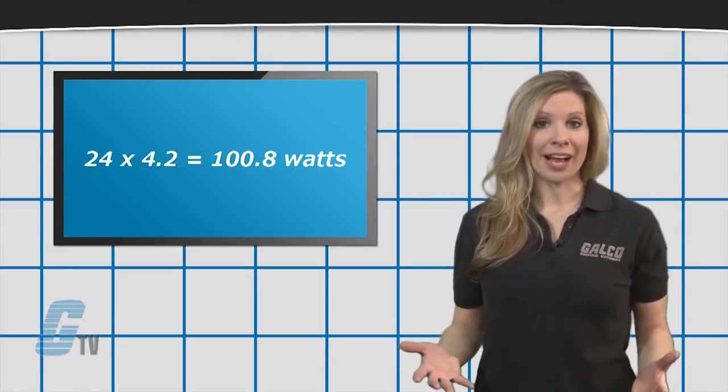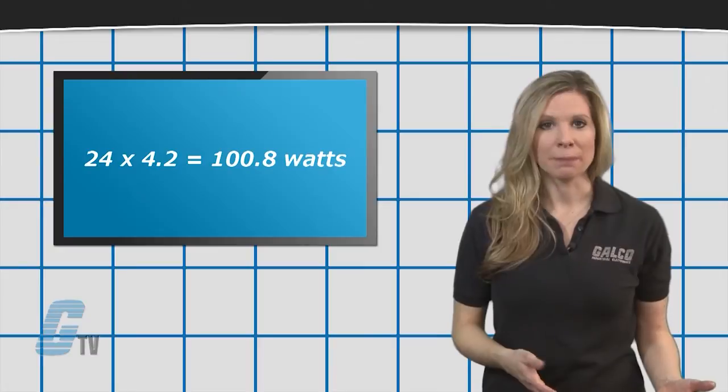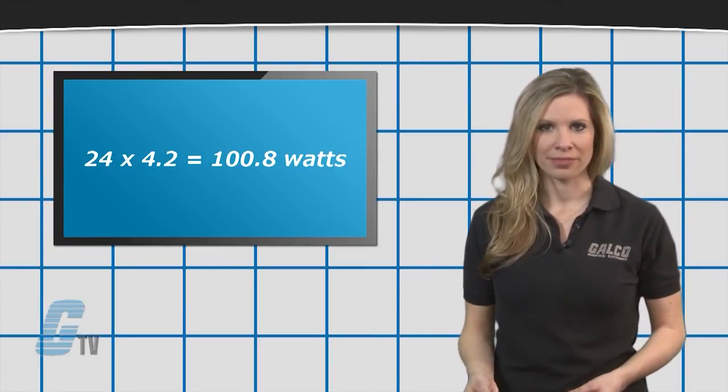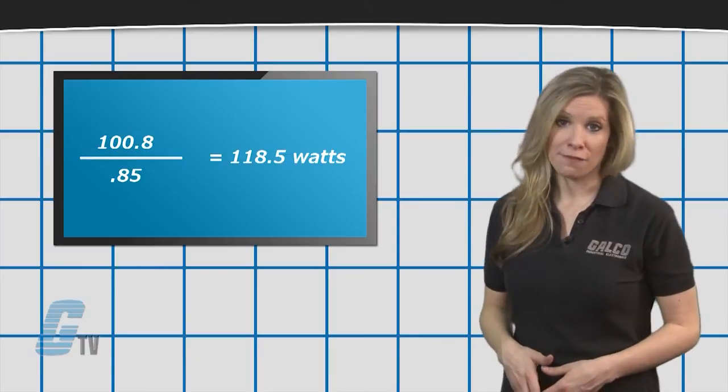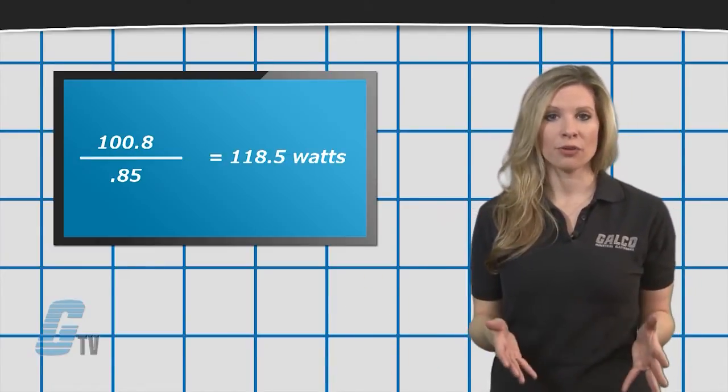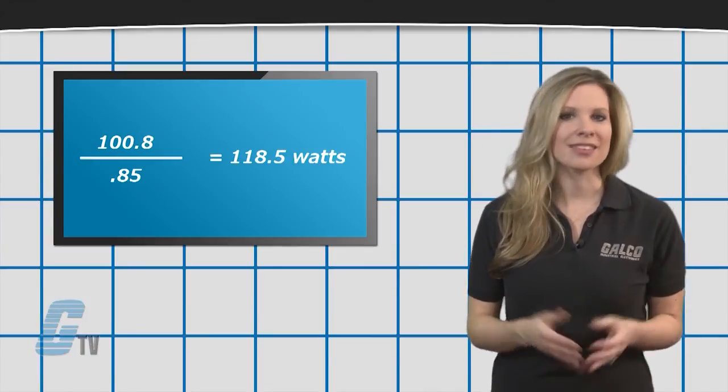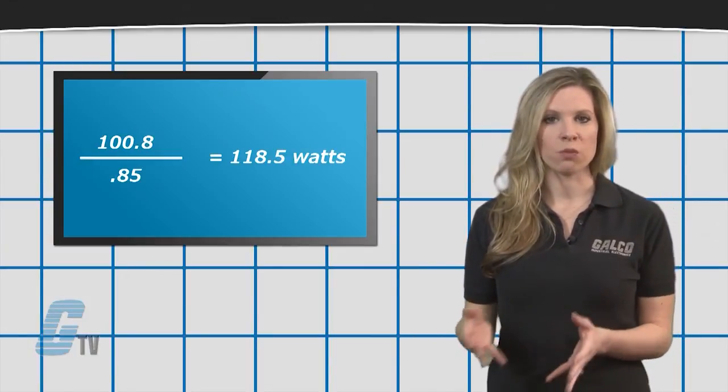Then I will need to find my effective input power by dividing the output power by the typical efficiency. If my efficiency were 85% and the output power is 100.8 watts, then my effective input power is 118.5 watts.